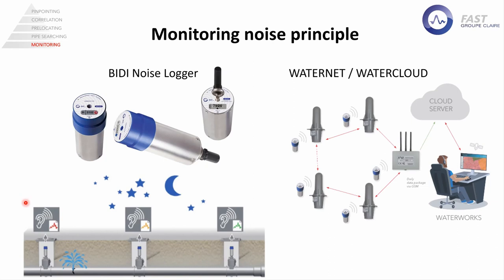Every leak is always growing; it won't get smaller. There are a few cases where this might not happen, if a rock falls down and blocks the leak again, but usually each leak is growing, and therefore we have more energy available to create more sound. With this sound, we can really precisely and accurately evaluate if a leak is present in the proximity or not.